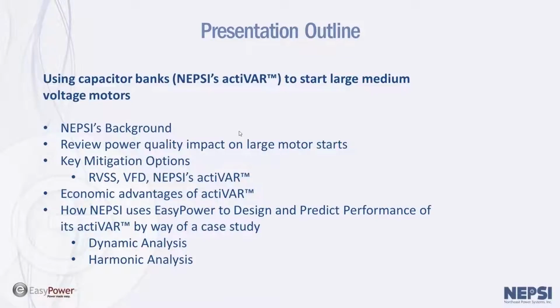We're going to start off with NEPSI's background, who we are and what we do, and then we're going to talk about the impact of large motors on power systems, and more specifically, motor starting. We're going to cover the typical mitigation options used to mitigate the power quality issues with starting large motors. The two key products currently used in the marketplace are reduced voltage soft starts and the VFD drive starter. We're also going to discuss NEPSI's actiVAR, which is basically a capacitor assisted motor start.